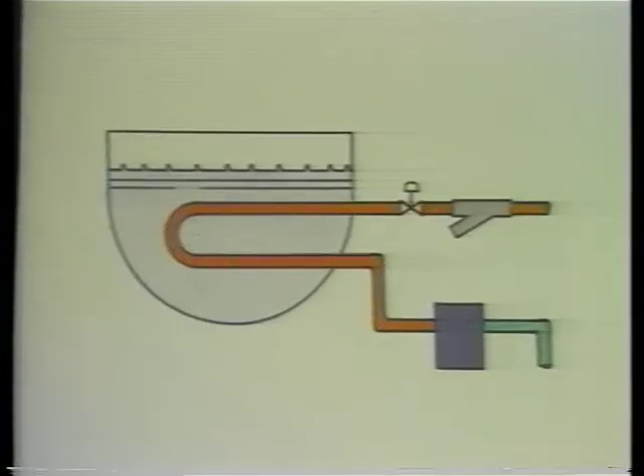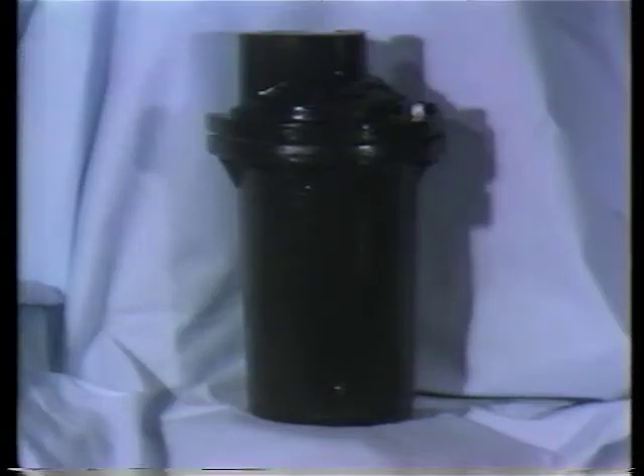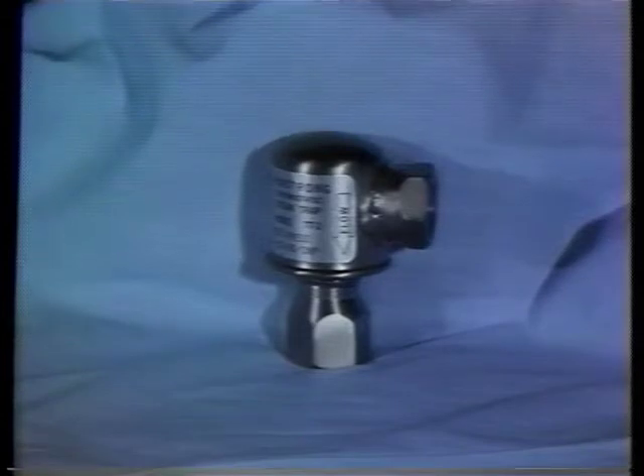Some of these kettles, particularly the storage type, are equipped with submerged coils. Here again, the inverted bucket trap will provide excellent performance. If the physical size of the inverted bucket trap is a problem because of serious space limitations, the balanced pressure thermostatic bellows trap is an acceptable alternative.